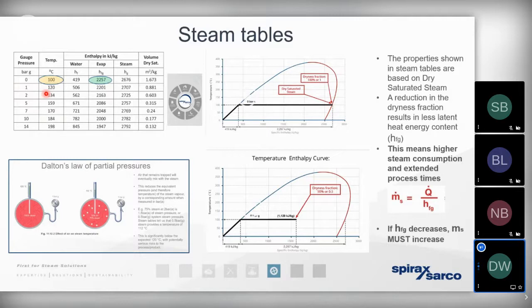But what we also know is the dryness of the steam is critically important. The steam tables are based on the assumption that the steam is going to be 100% dry. And in practical terms, that is very, very rarely going to happen. But what we've also said at the opposite extreme is that if we're not controlling, generating, or distributing the steam observing good working practice, then that steam could be very wet. And if we know the dryness fraction of the steam, then we know how much useful heat energy, how much enthalpy of evaporation, is going to be present within that steam.